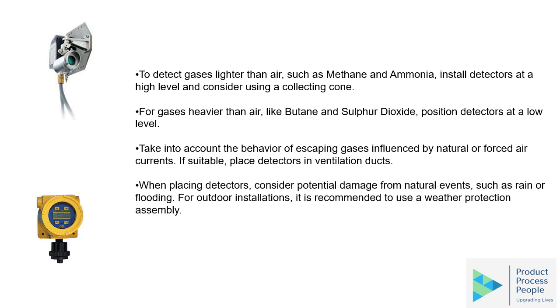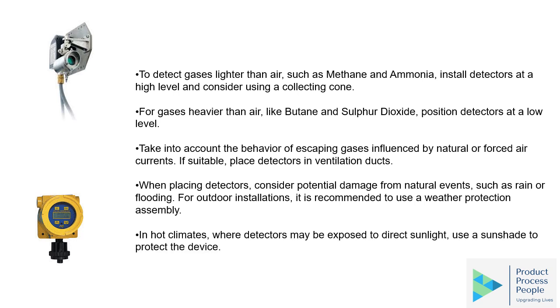When placing a detector, consider potential damage from natural events such as rain and flooding. For outdoor installation, it is recommended to use a weatherproof protection assembly. For indoor installation, try to install it at a convenient location. For hot climates where detectors may be exposed to direct sunlight, use a sunshade to protect the device.